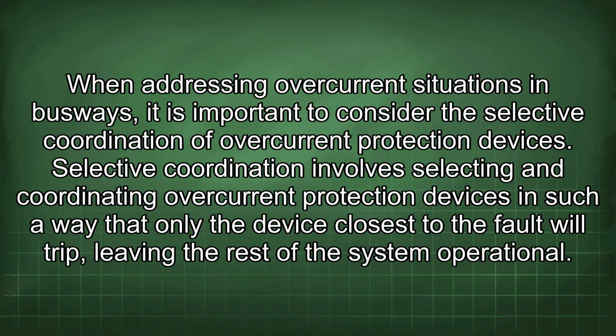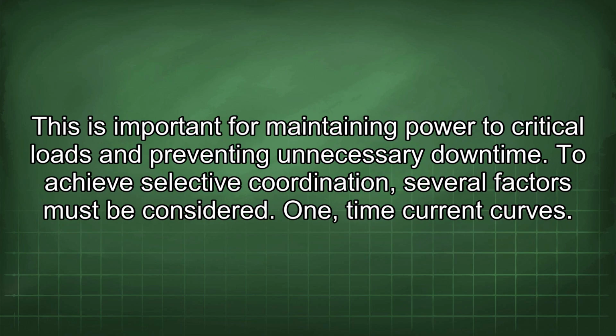When addressing overcurrent situations in busways, it is important to consider the selective coordination of overcurrent protection devices. Selective coordination involves selecting and coordinating overcurrent protection devices in such a way that only the device closest to the fault will trip, leaving the rest of the system operational. This is important for maintaining power to critical loads and preventing unnecessary downtime.